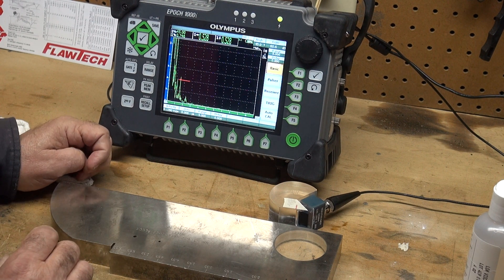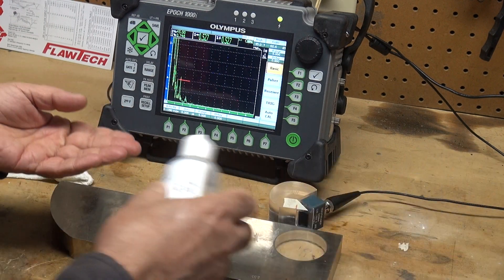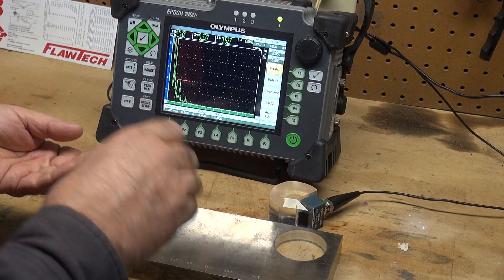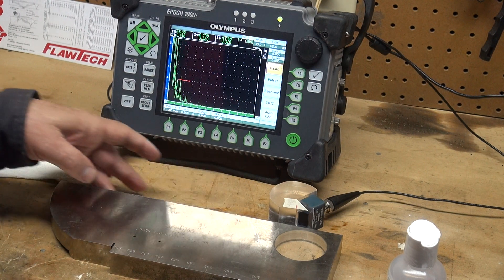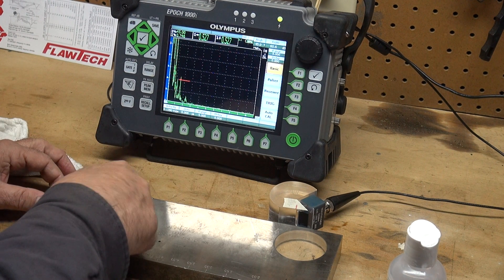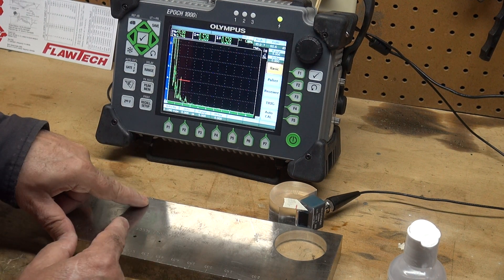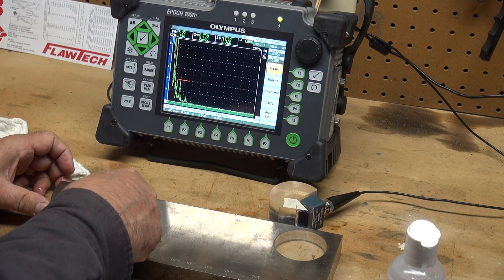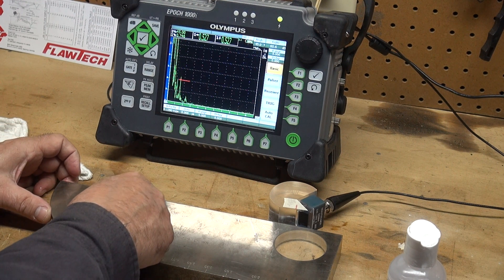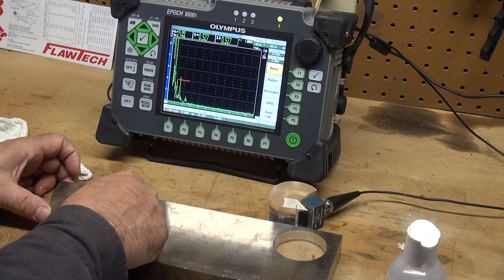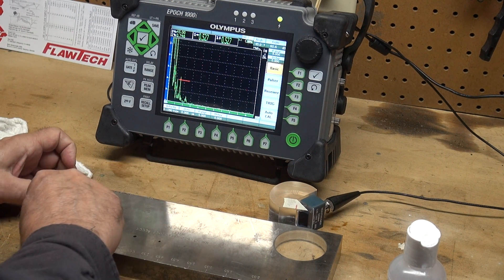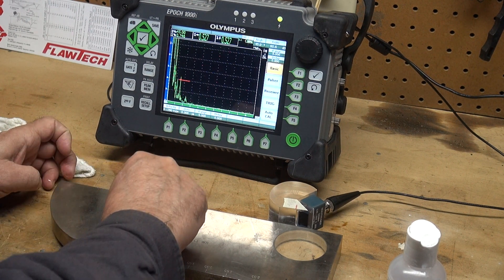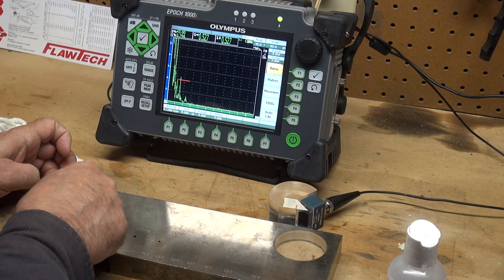I'm going to put some couplant on my IIW block. Right here is a zero marking, that is the machine mark on the IIW type 2 block. From this point to this radius is 4 inches and then on the other side is a 2 inch radius.